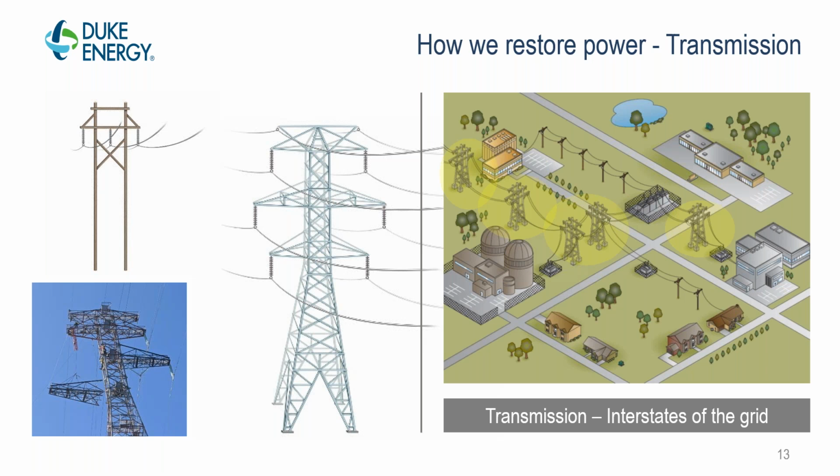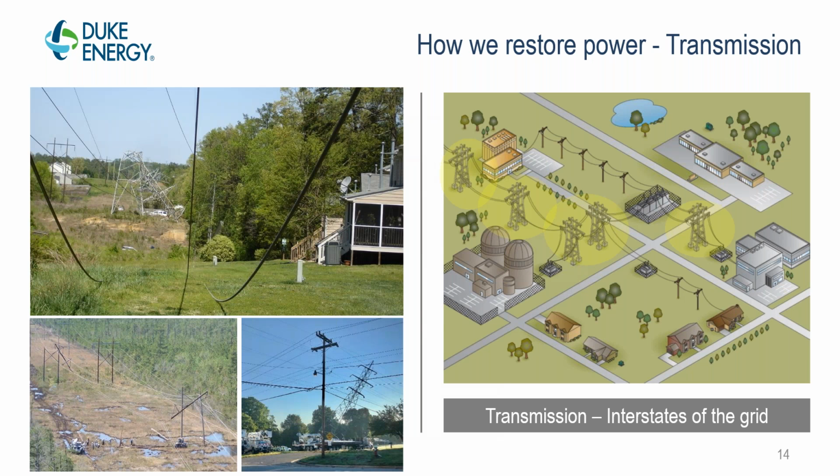As a part of that, one of the things that's very key is we have to be able to balance the generation load with how many customers we can get back online. And so there's this balancing act that our energy control centers manage around generation plant availability, getting the generation plant online, understanding what transmission lines are out or not out, which ones can actually take load, and making all of that picture balance out. So there's a lot of complexity there, from a technical standpoint, in terms of getting that generation transmission backbone up and running again following a major event.